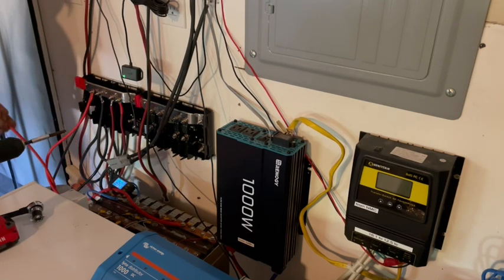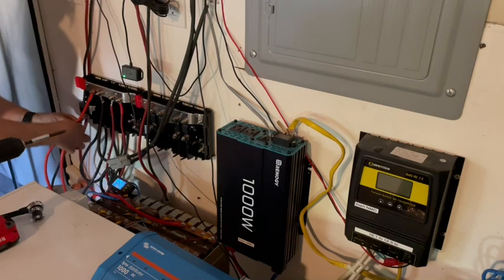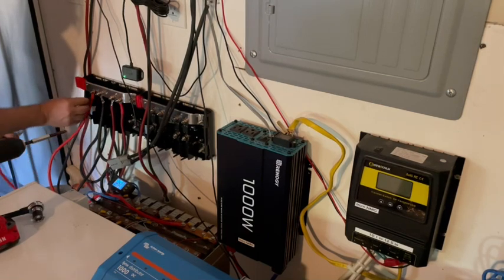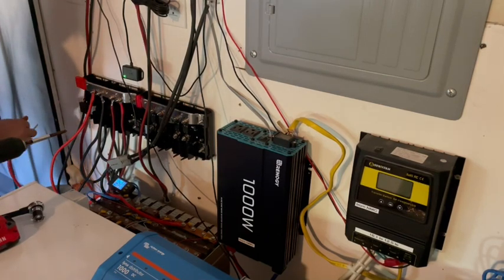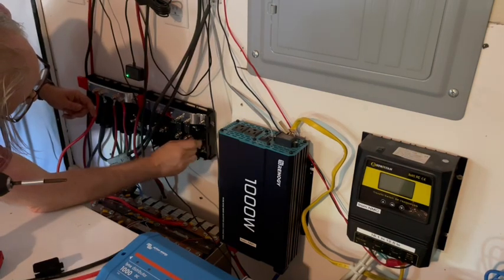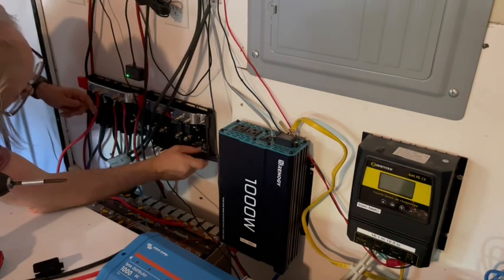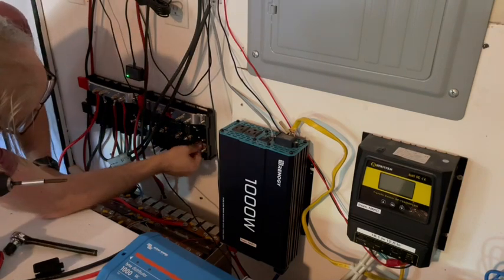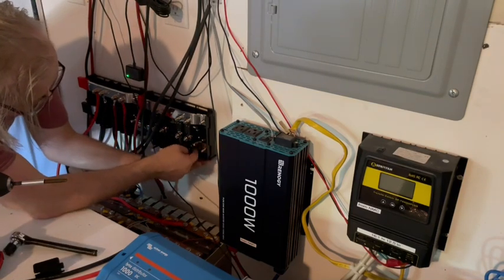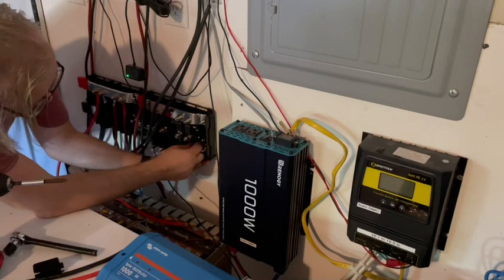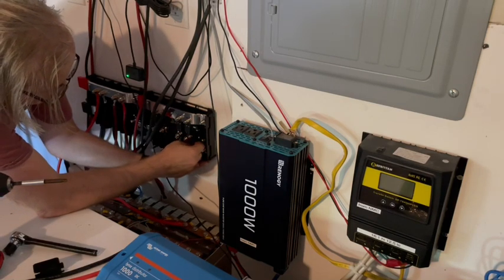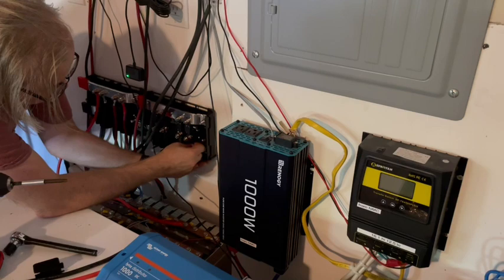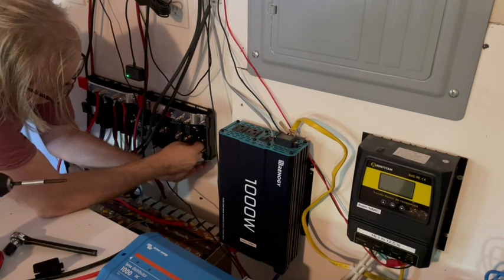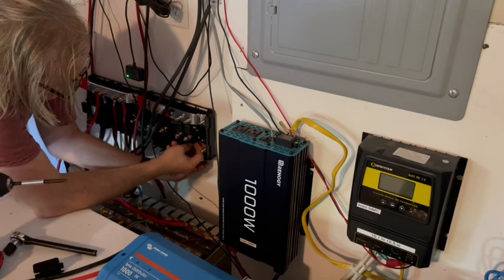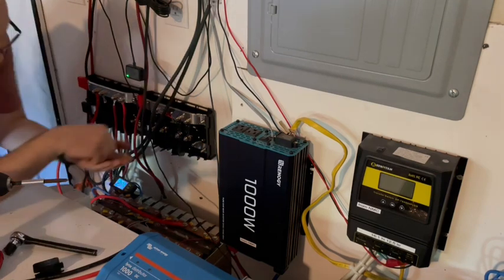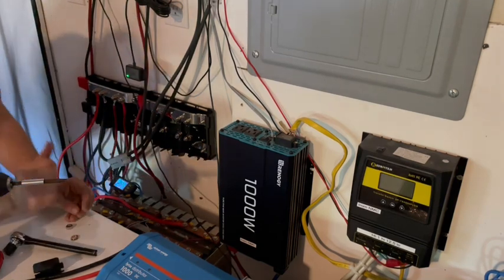So this is my battery lead, which is going to stay here. Now this inverter will be fused. It's a slow blow fuse because there will be some significant inrush current capability from the DC-DC converters in between, and also the capacitors in the inverter itself. So if you were to have a fast blow fuse here, even though it's high capacity, it might actually blow.